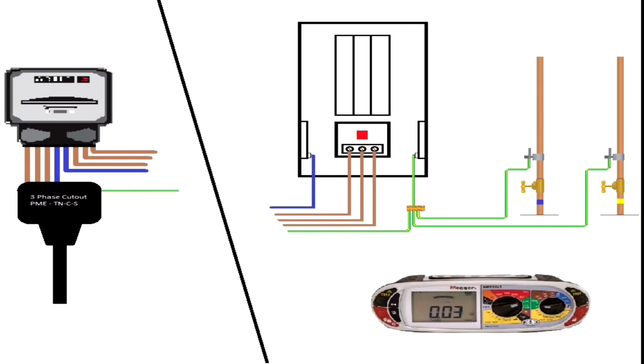So let's break down what we could have at AM2, AM2S, AM2E. Main supply on the left-hand side, TNCS, TNS earthing arrangement, whatever it is. And we've got an MET now. In the video I'm going to show you at the end of this one, Matt didn't have an MET. He had all the bonding conductors and the earthing conductor within the distribution board. We can see there, metallic water, metallic gas, it might be metallic structure of the building, offering parallel earth paths. So removing the earthing conductor within the distribution board wouldn't remove those parallel earth paths. So you're going to have to remove it from somewhere else before doing our external earth fault loop impedance.